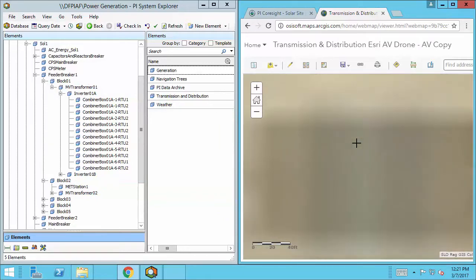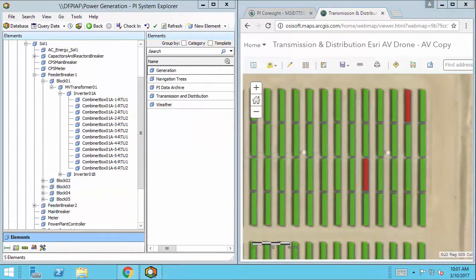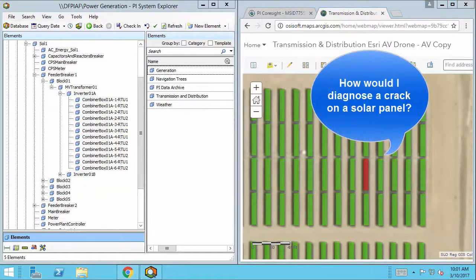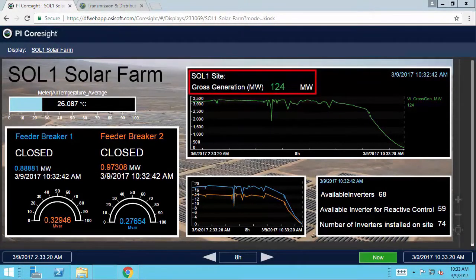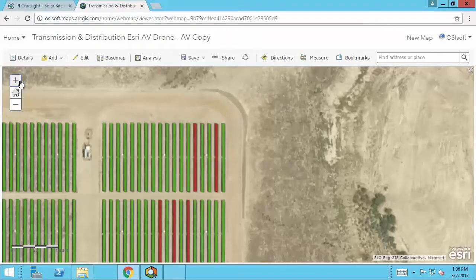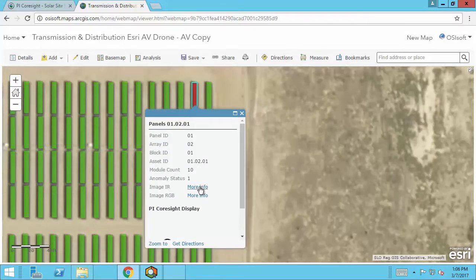You can see the map location blocks and the representation down to the solar array. Now let's take a look at a specific use case: how would I diagnose a crack on a solar panel, and how do I identify and replace a batch of faulty solar panels? I'm an operator from Sol One Solar Farm and notice generation is way down — this is an issue because I recently signed a power purchase agreement with a local municipal utility company to provide 250 megawatts. After confirming the loss in power on the PI Coresight display, the AVDSS application will update a feature layer that will identify the problem area. Immediately, I see the solar panels in red that are causing the generation loss. Clicking on the pop-ups shows the imagery picked up by the drones.